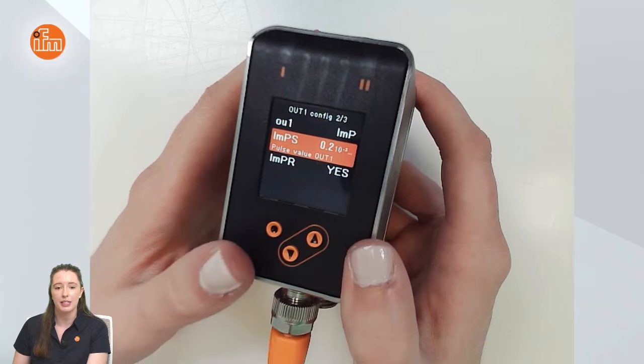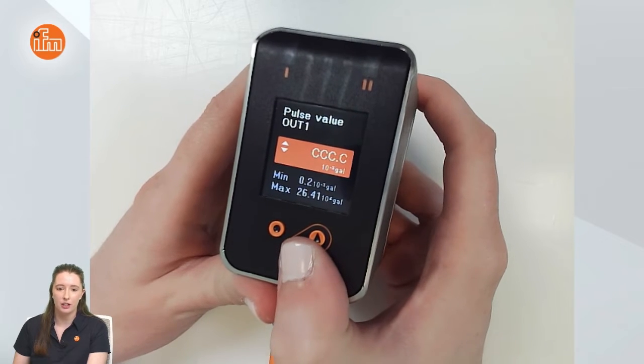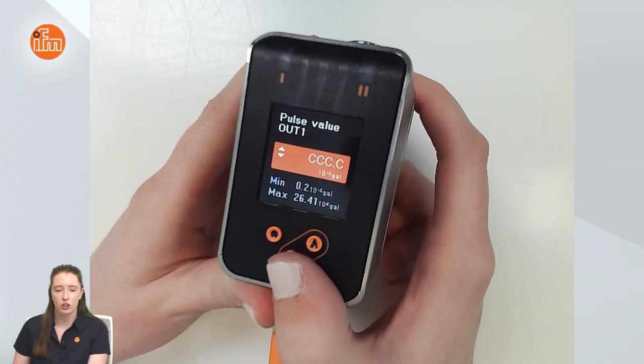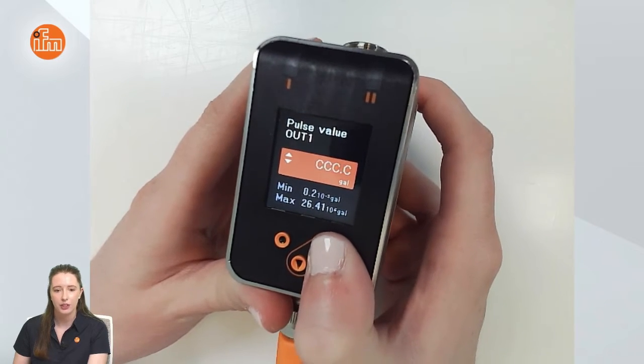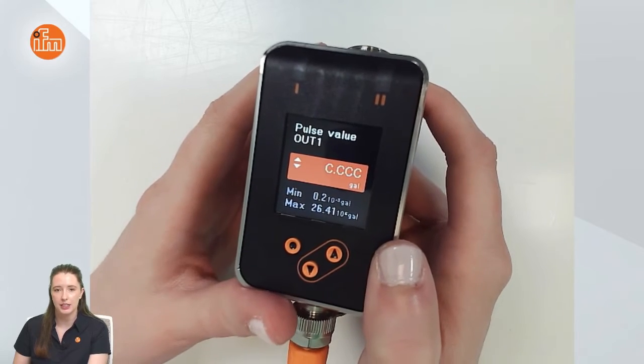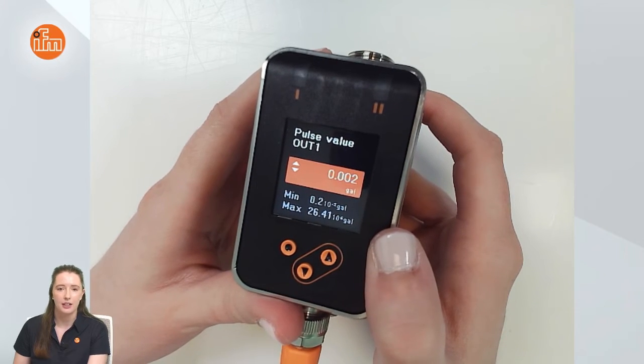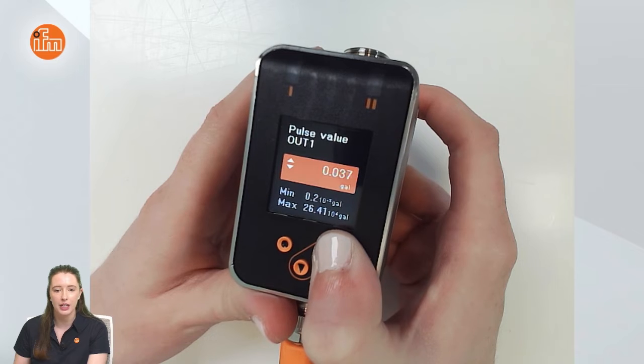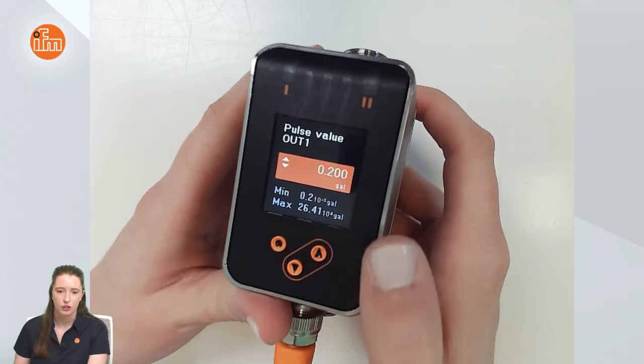Let me take you into the IMPS parameter by pressing enter once IMPS is highlighted. Press down either the up or down arrow key until the bar loads. The first thing you will see in the IMPS parameter is C's across the screen, and you can set your factorization or decimal point at which you want to set your IMPS value. In this video I'm going to set it for 0.2 gallons, so once I have C.CCC — and you can see it is in gallons — I will press enter. It is currently set for 0.002 gallons, so I'll hold the up arrow key to scroll and set it for 0.2, then press enter.